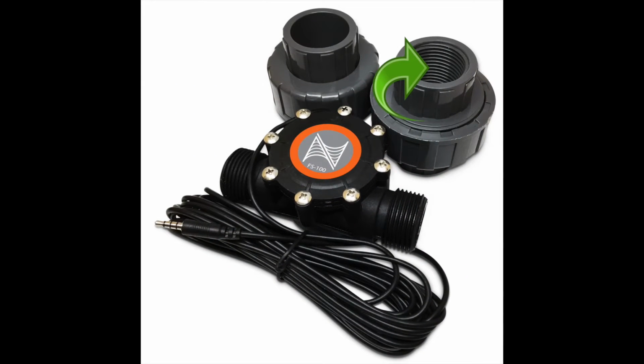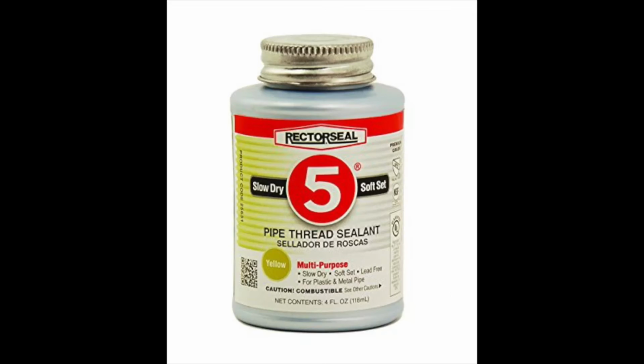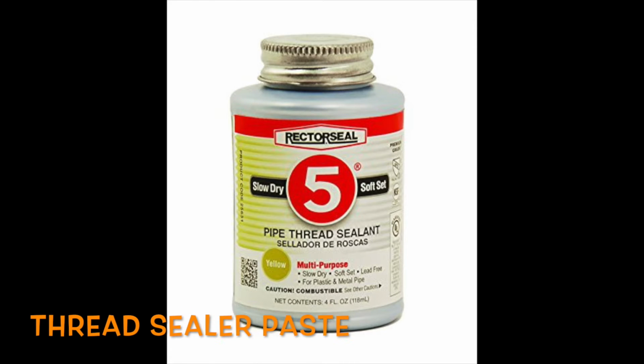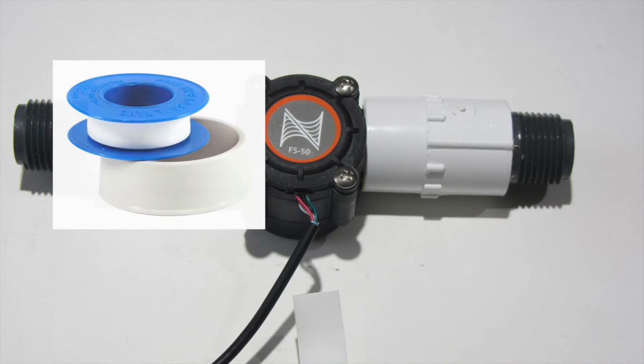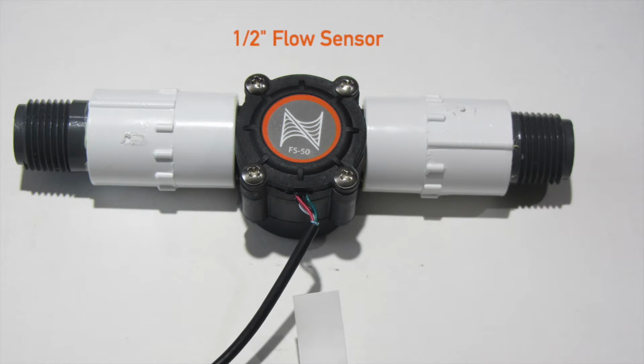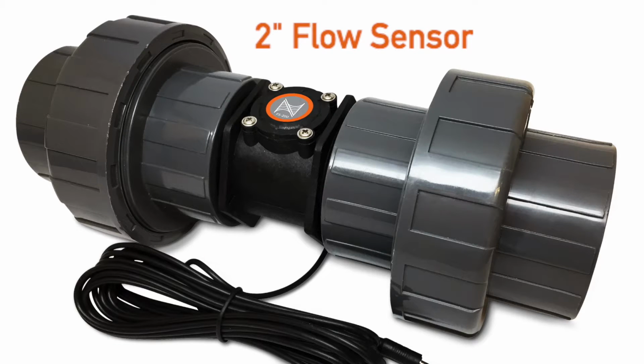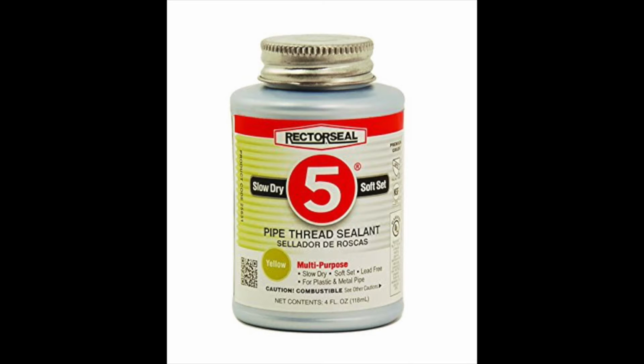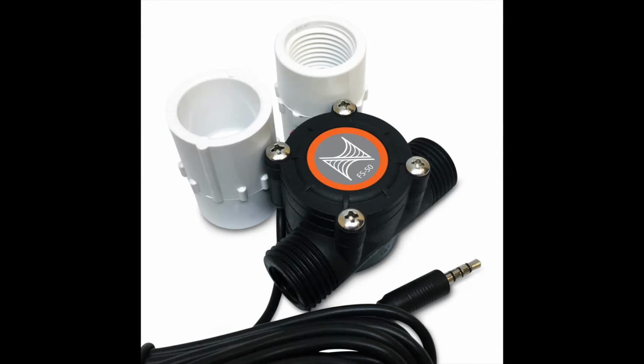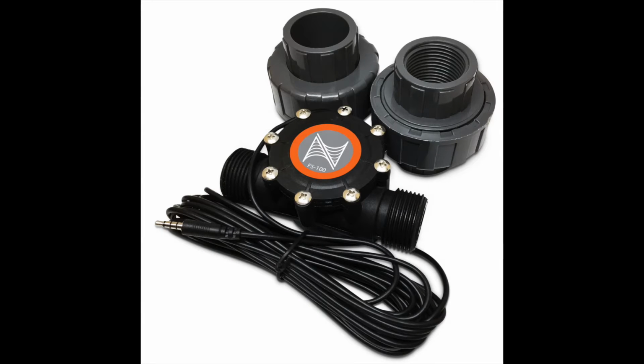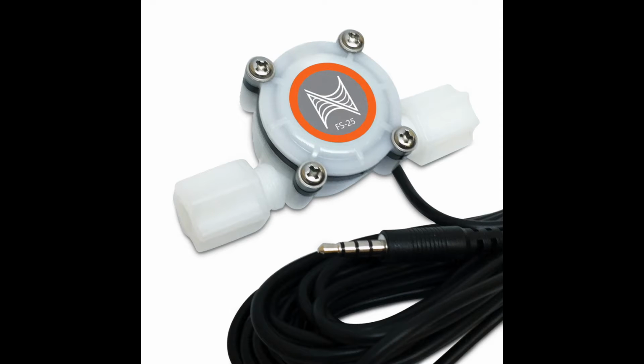When attaching the plumbing fittings to the flow sensor, it is recommended to use a thread sealer paste to prevent water leaks. Thread sealer tape can only be used on the half-inch flow sensors, but if you're installing a 1-inch or a 2-inch flow sensor, it is mandatory to use a non-hardening thread sealant such as RectorSeal 5, and it is best to use this on all our sensors. Teflon tape or PTFE paste should not be used on the larger fittings. The 1/4-inch flow sensor uses a compression fitting, so no sealant is needed on these sensors.